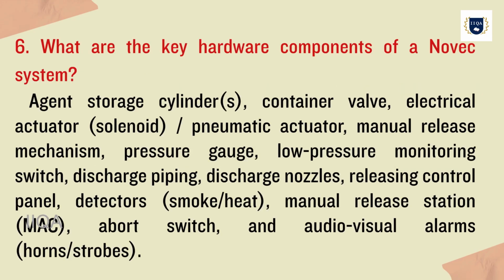6. What are the key hardware components of a Novec system? Agent storage cylinders, container valve, electrical actuator, solenoid pneumatic actuator, manual release mechanism, pressure gauge, low pressure monitoring switch, discharge piping, discharge nozzles, releasing control panel, detectors (smoke, heat), manual release station, MAC, abort switch, and audiovisual alarms, horns and strobes.